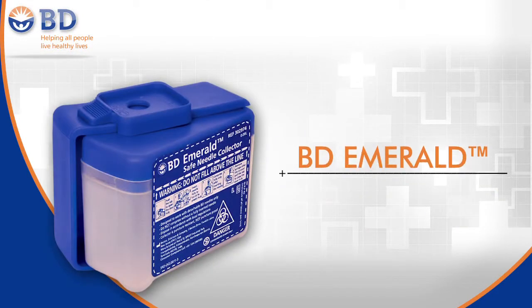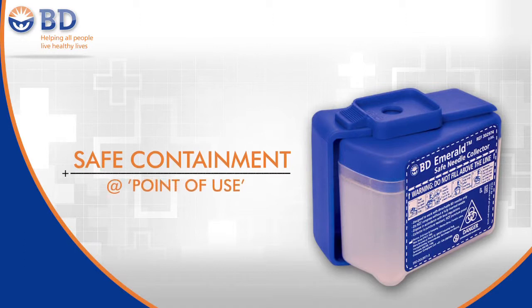BD introduces for the first time in India a point-of-use disposal solution. BD Emerald Safe Needle Collector cuts the hub of the needle to safely contain the needle until final disposal, thereby preventing reuse of the needle. Finally, safe containment at point of use.